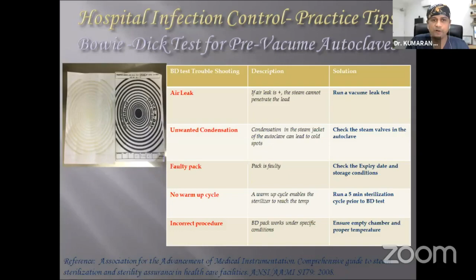And ensure that you run the linen inside an empty autoclave, because this basically ensures that all the air inside the autoclave is removed and that the paper changes color. You need not run the entire autoclave cycle. The dry time is not needed. Once the initial temperature is reached, then you can go ahead. So this is then a chart which shows the troubleshooting of the Bowie-Dick test.